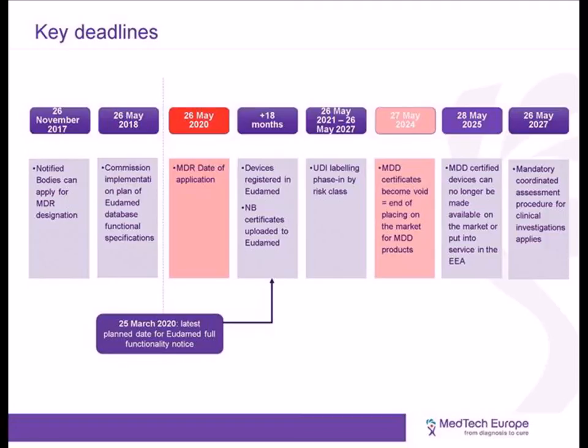Companies should note that the obligation to put UDI on device labels is separate from the obligation to assign UDI to devices, separate from the obligation to register UDI information in EUDAMED, and to include UDI information in regulatory documentation. In other words, UDI obligations are different and will apply at different dates and therefore must be planned for independently.